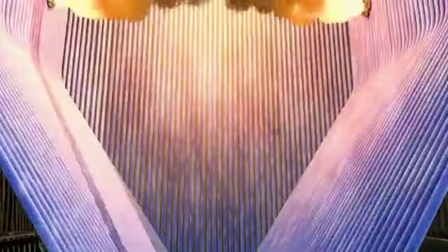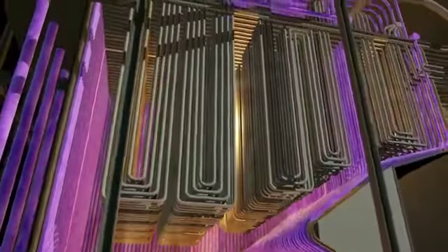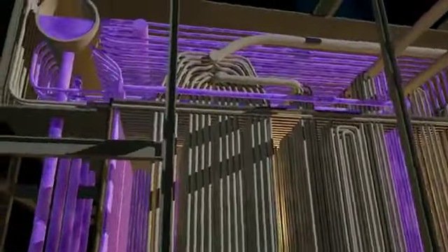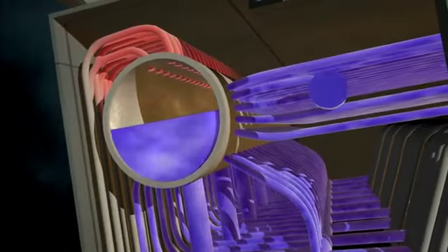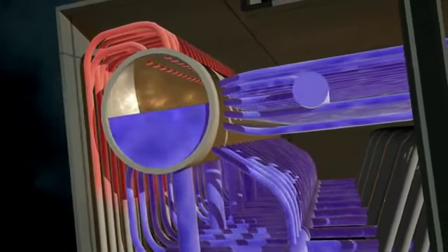A network of 2-inch tubes line the firebox walls, and burners force-feed a continuous supply of combustible fuel into the ultra-hot firebox. Eventually, the insides of the firebox burn so hot that its surrounding steel walls would melt if not for the tube-lined walls of liquid water. At the point in the cycle when the liquid water turns to steam, the steam separates and collects at the top of the steam drum.